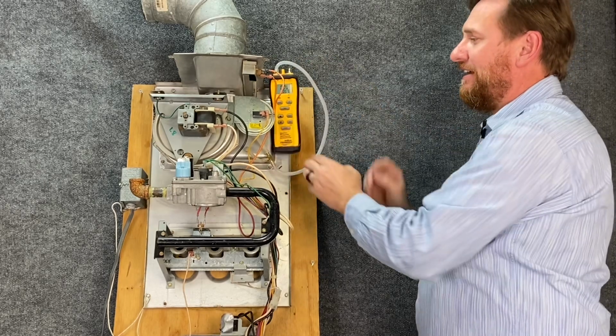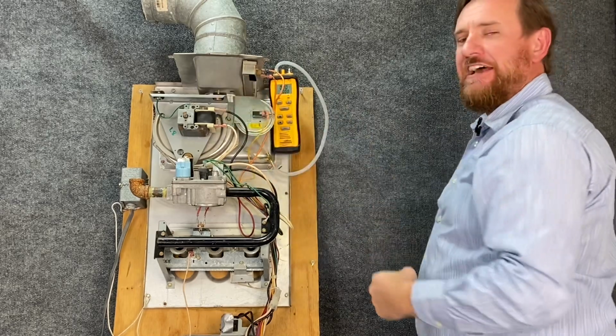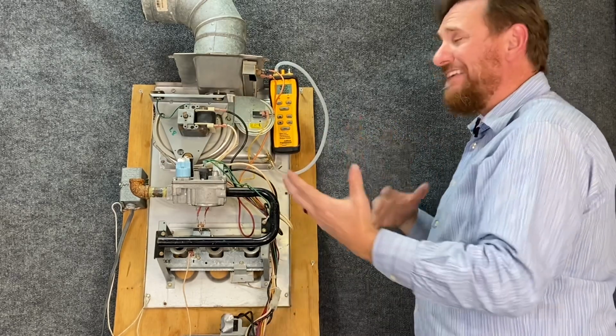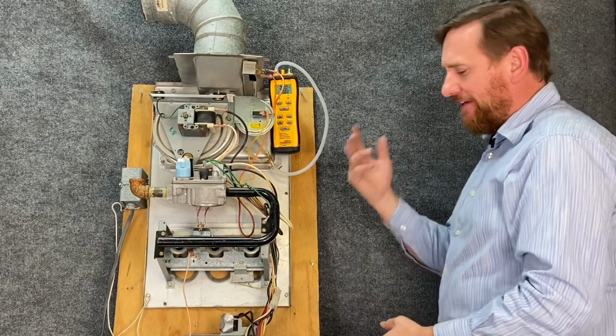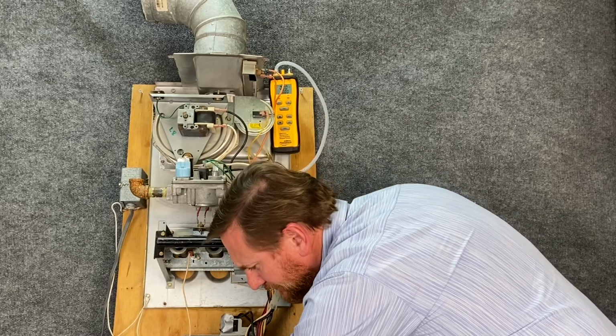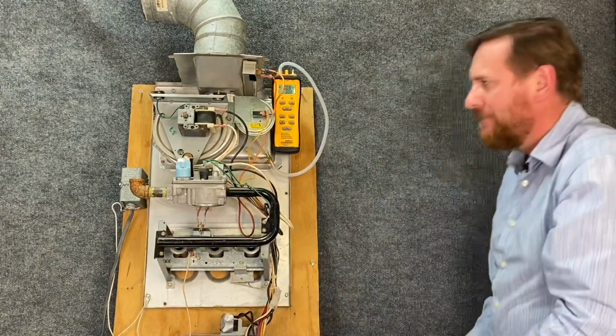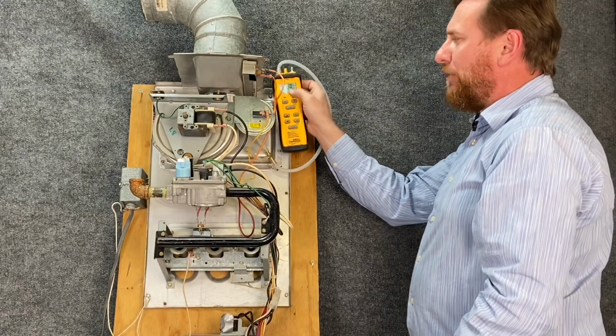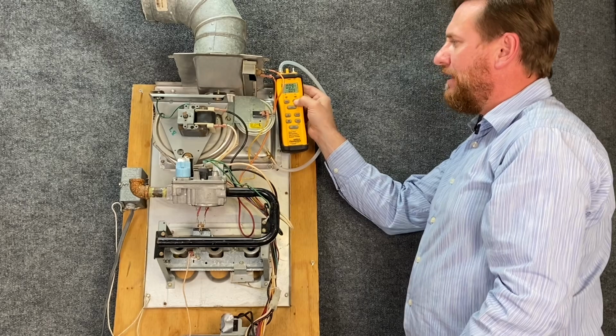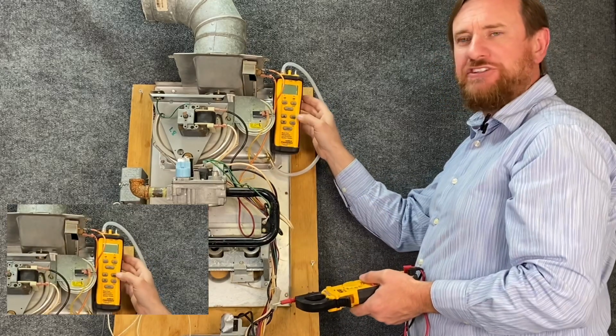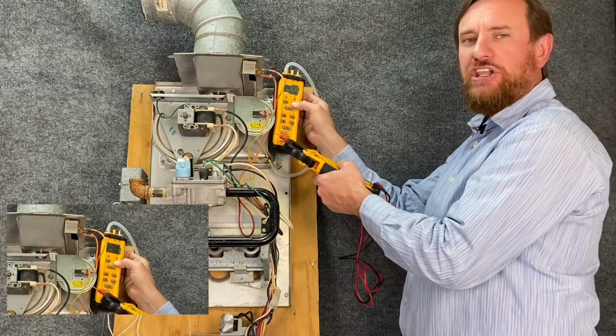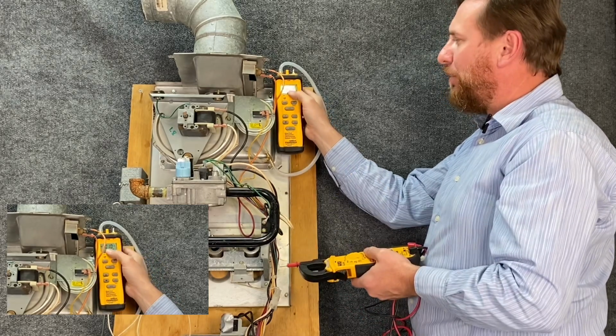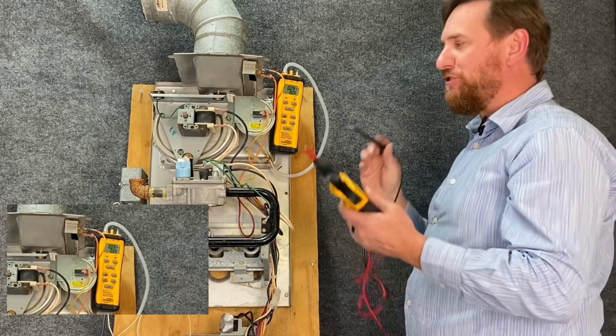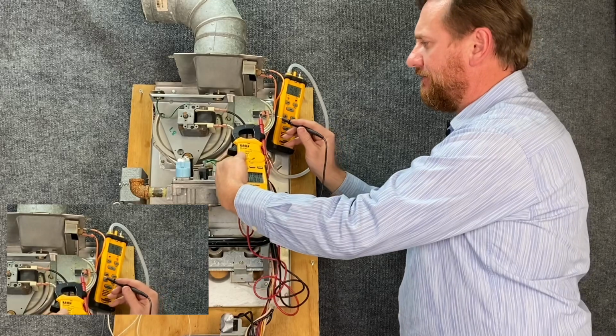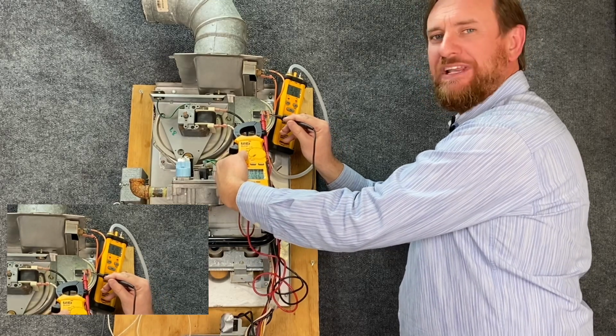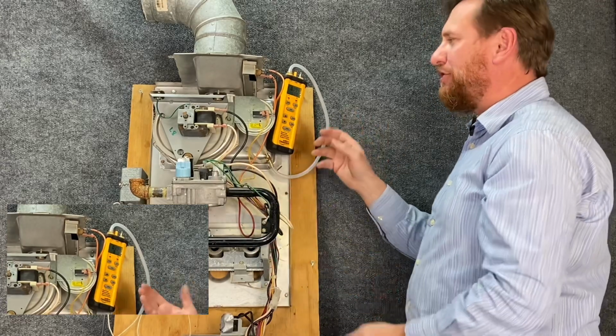So what we're going to start with is see, is the switch good? Is it bad? Are we getting enough vacuum? My control board, the switch, is it closing? What's happening? Let's find out. We're going to have a call for heat and go through our sequence of operation. Now our inducer fan motor is working, but we're pulling 0.1 inches of water column. This switch is rated at 0.25 inches of water column. So the switch right now is not going to close because I do not have enough vacuum going to it. At 0.10, the switch should be open, which means I should read voltage. Let's check. I'm reading 27 volts, so I know my switch is open, and it should be open.